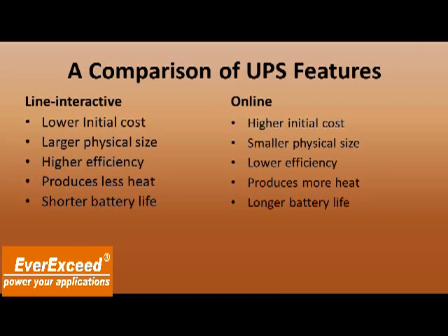There are less circumstances for the online to actually be going into batteries. And some batteries are under less stress. Typically, there's a longer battery life on the online. And that can actually make up totally the difference in the initial cost. As we said, the line interactive would spend more time in the battery than the online.